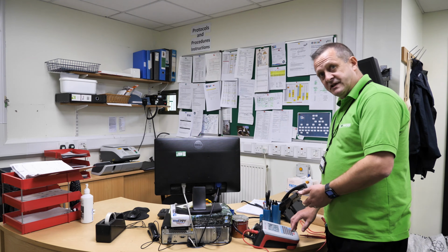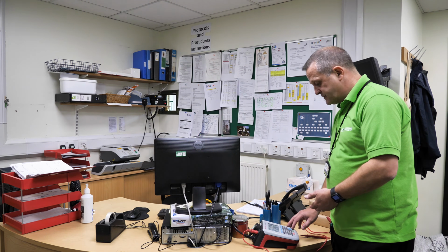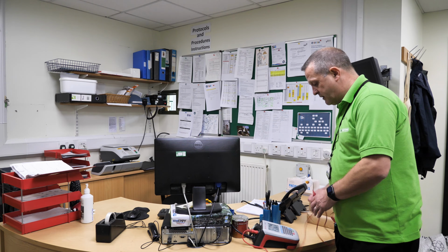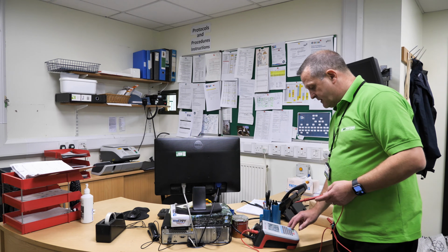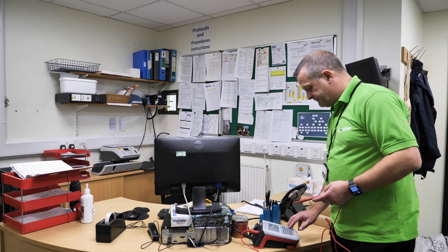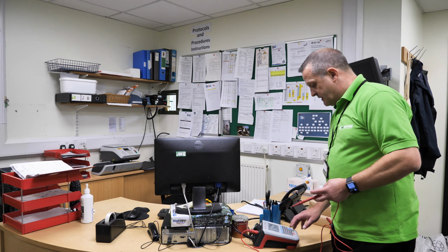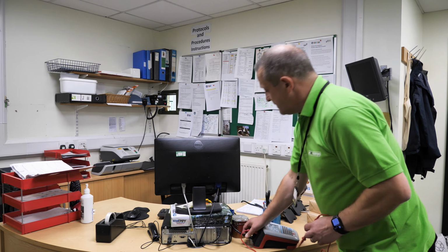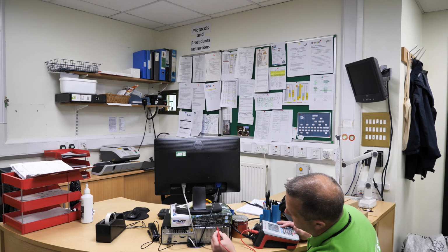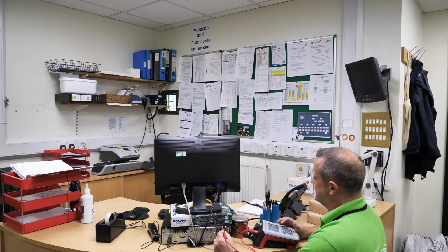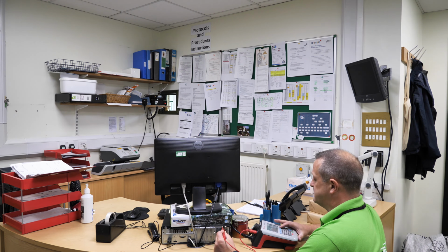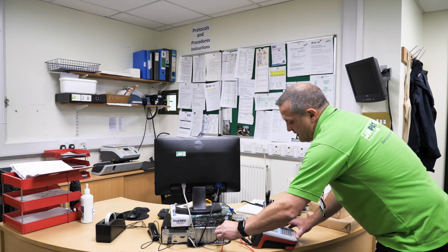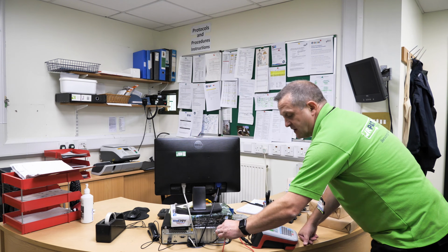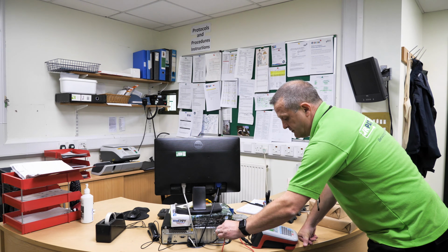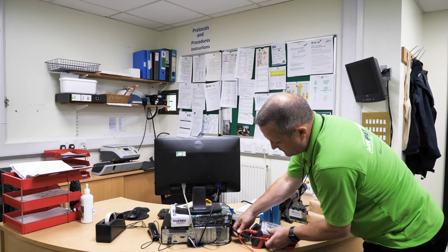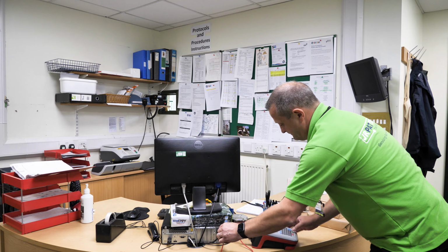So again, this particular device has got a number of pre-programmed tests, and one of them is a Class 1 IT equipment test. So I'm going to select that on here, and then we're just going to run through the test. So again, finding some exposed metal parts on the computer base station, we will then run through the test. And that's much safer because it's just going through at 250 volts rather than the standard 500. And this is where I need to then plug in to test the PE current.